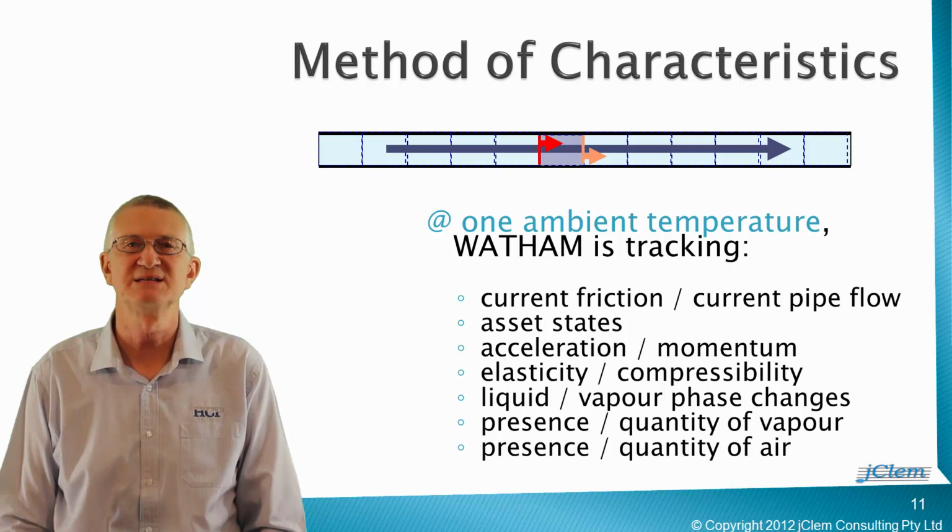It's important to understand that WATHAM operates at a single ambient water temperature. WATHAM cannot include thermodynamic effects related to changes in water temperature. At a single temperature, it is tracking at each time step the current pipe flow and adjusts the pipe friction accordingly. And of course, it tracks the operational state of all the engineering assets such as water level in tanks and pressure vessels, air inflow or outflow rate at air valves and standpipes, opening position of valves, and the current operating speed of pumps, etc.